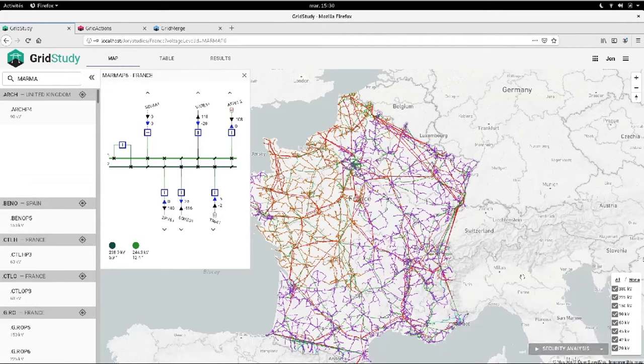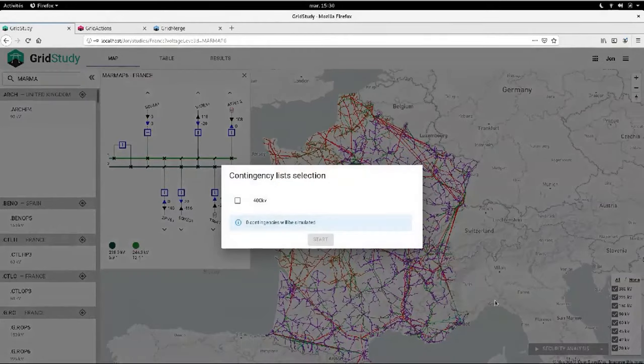Running a security analysis means checking one by one for a list of predefined contingencies, whether or not they affect the network. For example, in this case, I could ask for the platform to run a simulation for in case each of the lines of the 400 kilovolt lines in the network had a problem. So this would mean running for this network 867 contingencies and getting results on which lines, when they have a problem, cause disruptions in the network.